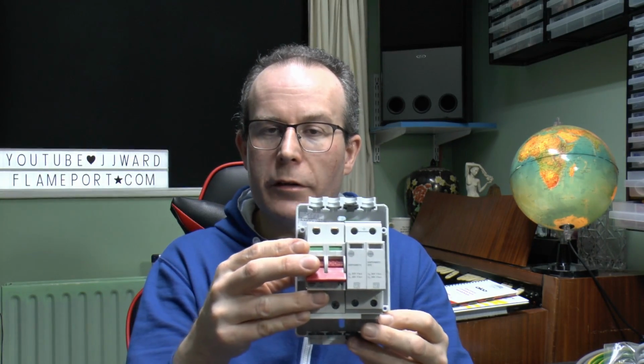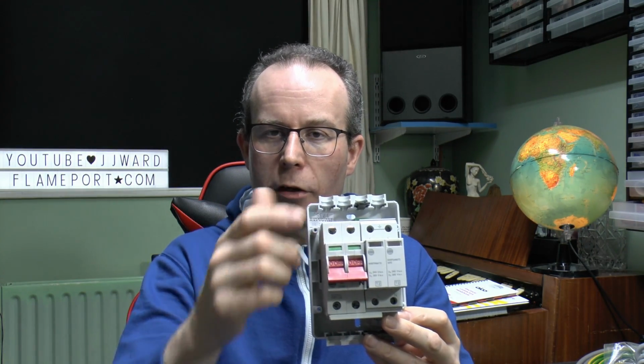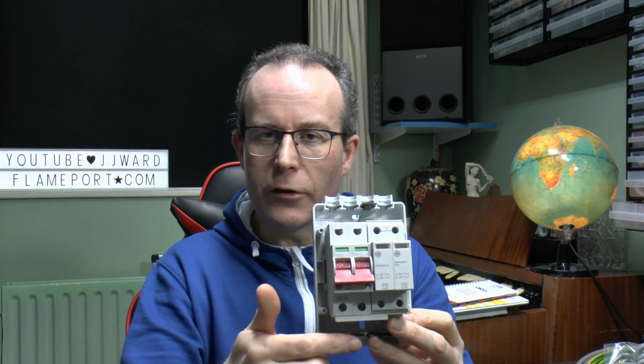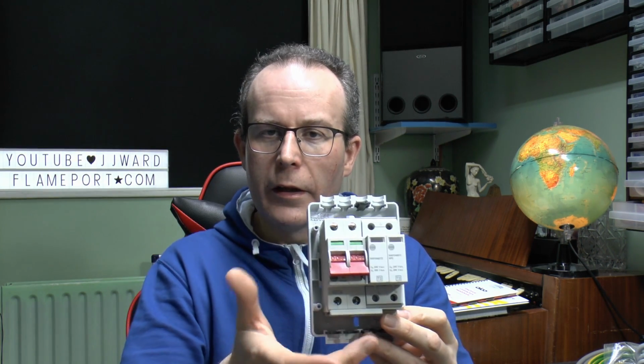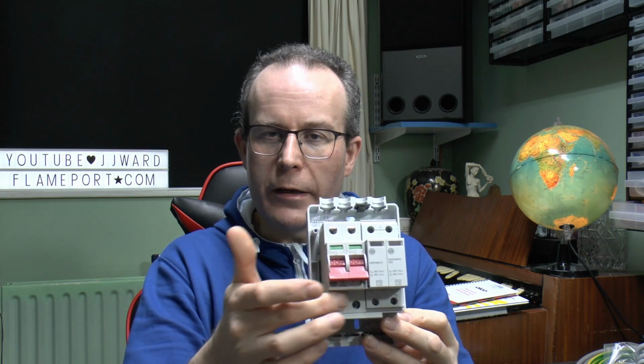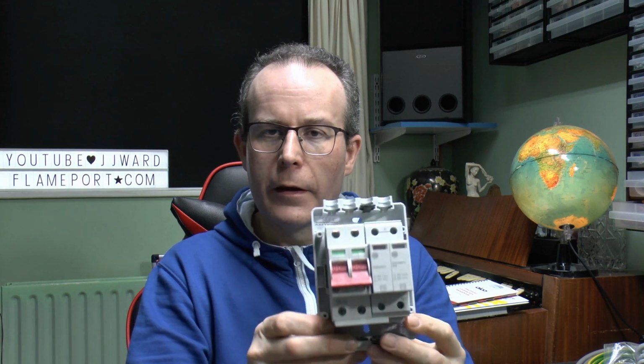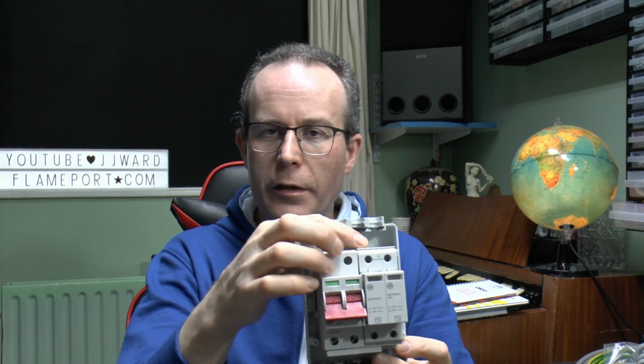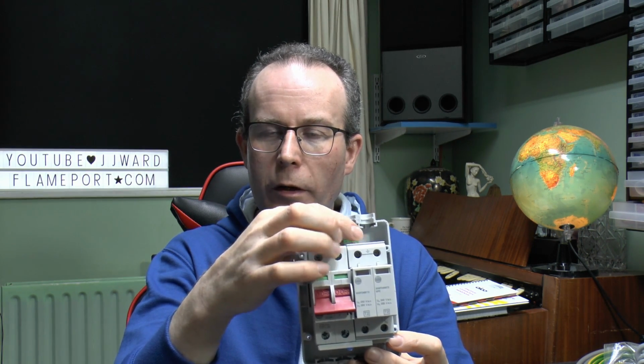If this was a consumer unit, pretty much the same deal. That was your main switch in a consumer unit. Supply coming in the top, out the bottom is your bus bar, and then your neutral going up to the neutral bar. And again, it's the same deal. It's right next to those conductors coming in. So again, it's just those tiny short pieces on the bottom. Other thing to consider here though is that in a consumer unit you'd have your single earth wire from here to the earth bar in the consumer unit. That distance is part of it.